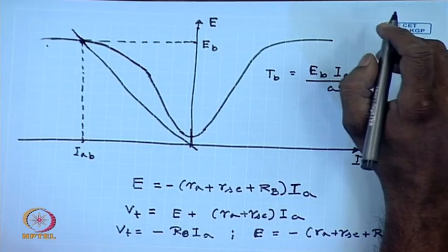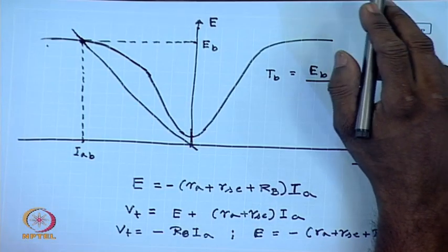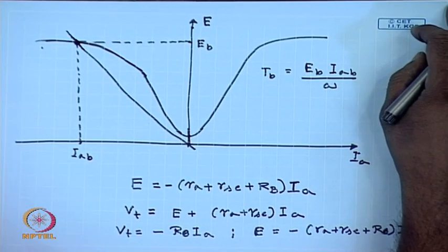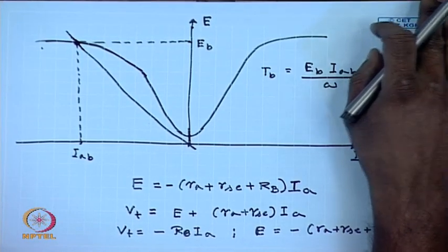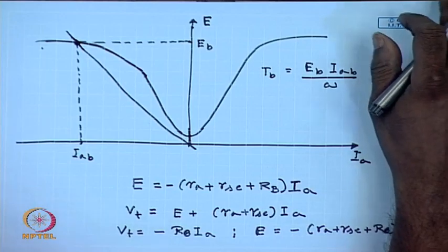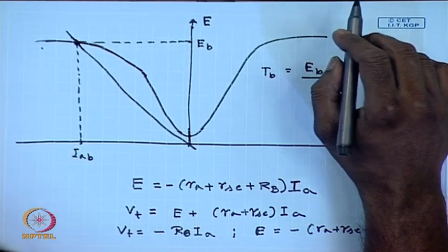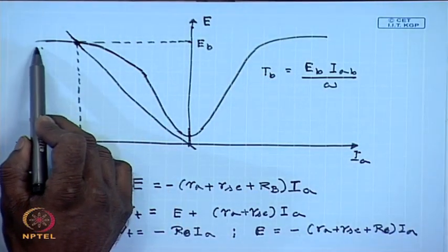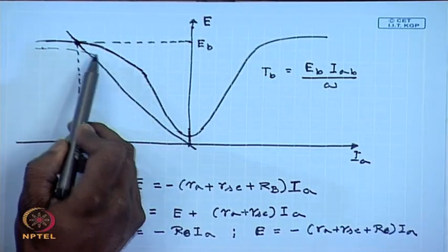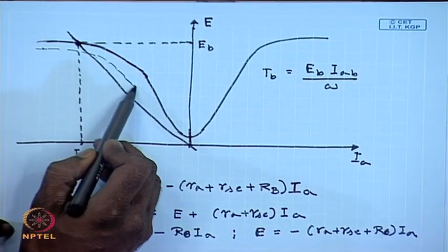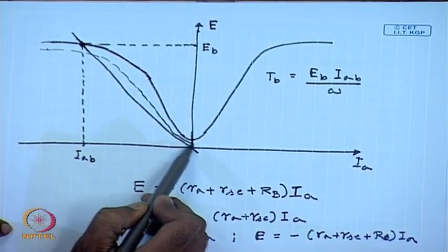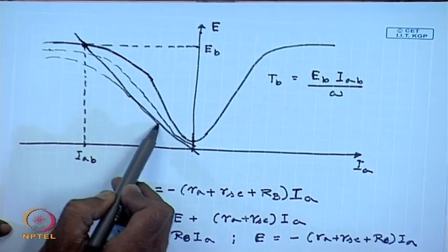It should be noted that during braking, the series motor operates as a self-excited series generator. Hence, it will have its self-excitation, critical resistance and critical speed. So, as the machine speed goes down, the OCC will also decrease, and at some time it will become tangent to the load line.